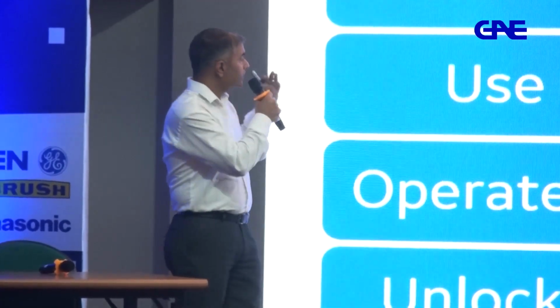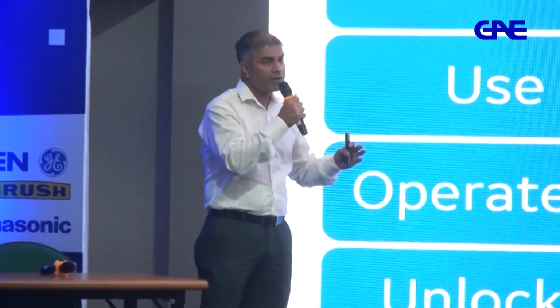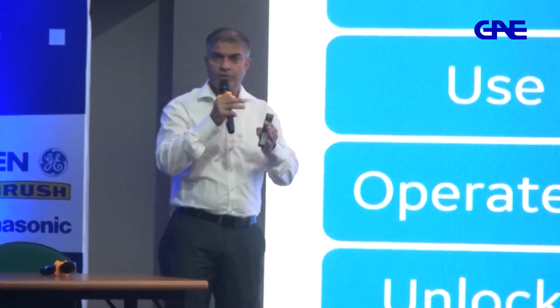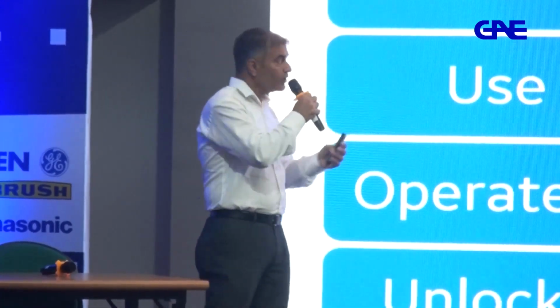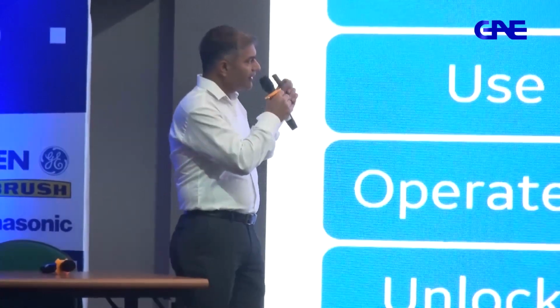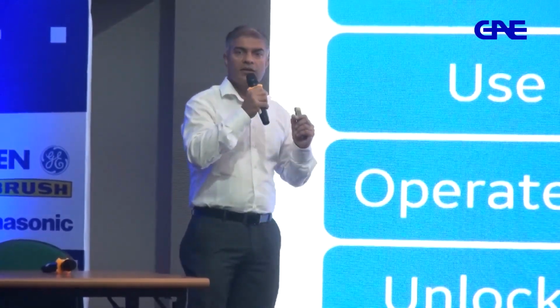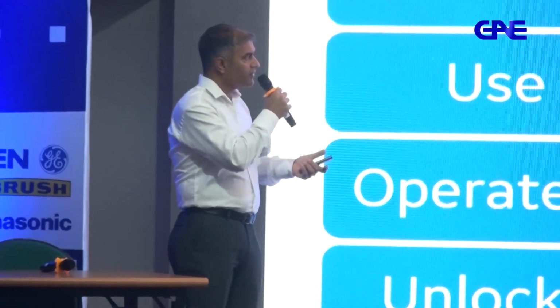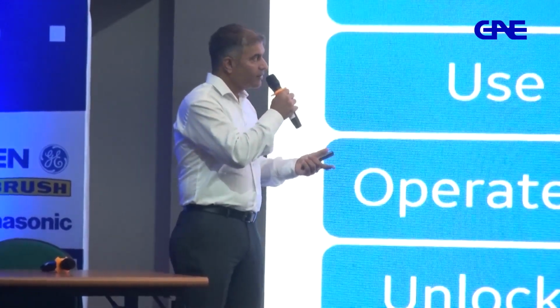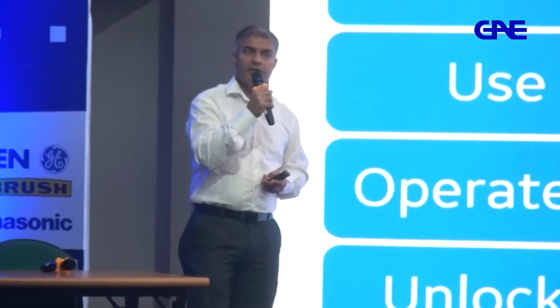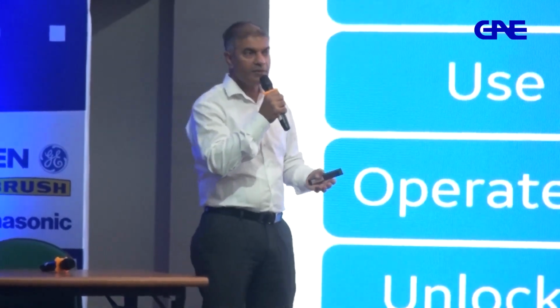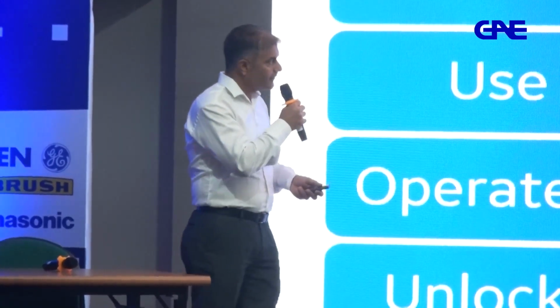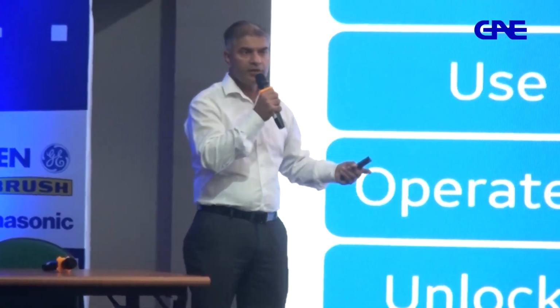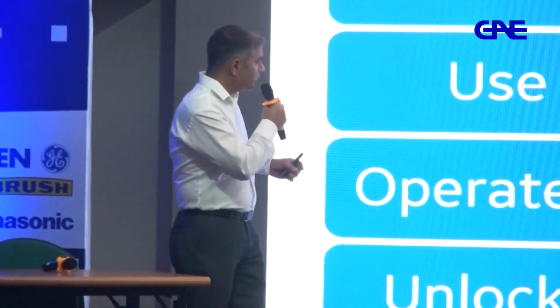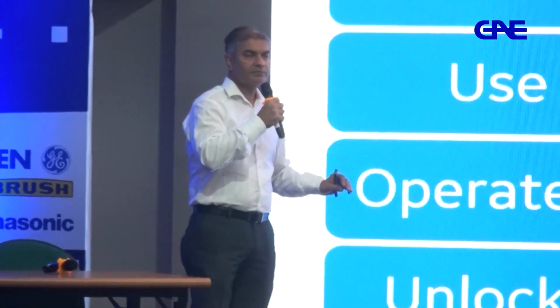You can reduce installation time and commissioning time, you can modularize and use design modules. You use less infrastructure, less wiring, less cable trench. Instead of copper cables, you use cable trench with fiber optics, so you can reduce that. You get smaller buildings, smaller yards, and, as I'll come to later, better operation.